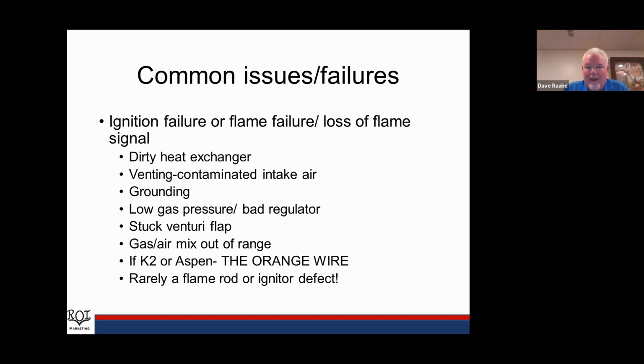Some of the causes for this could be a dirty heat exchanger. So again, having a boiler that hasn't been serviced properly. It could be venting. It could be that we're pulling in exhaust into our combustion air. We could have low gas pressure or a bad regulator. I've run into bad regulators on propane installations. It could be a frozen regulator if we're having very, very cold conditions.